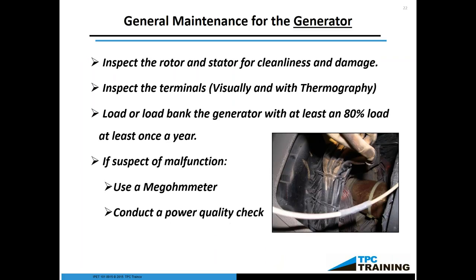On the generator itself — we have a picture here of a mobile generator. Inspect the rotor and stator for cleanliness. This one is old; you can see the shaft of the rotor is a bit rusted, but it works just fine — it isn't overly corroded and you don't see metal chipping away. There's a little dust in there, but no rats made a nest, no birds living in there. Sometimes if a generator is located remotely, animals want to make a nest in there — so that's what you're looking for. Inspect the terminals especially if your generator is a mobile generator located outside, as it becomes susceptible to the ravages of the environment and will corrode. Clean off that corrosion, but as soon as you see any pocking of it — holes being formed — those terminals are done, because the resistance has gone up and they are no longer suited for having electricity going through them.